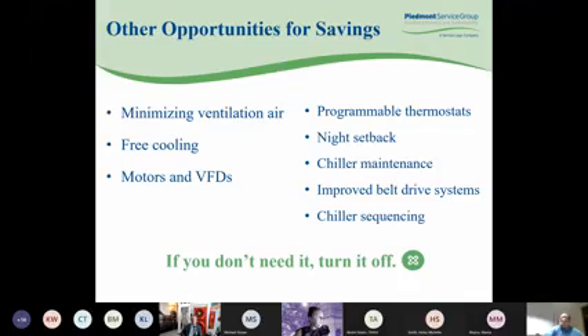Premium efficiency motors is another area. The difference in operating cost between a 92% and a 93% efficient 20 horsepower motor can be between $50 to $120 annually. The variable speed motors is another area that we can look at. Rewinding failed motors is not cost effective in high use applications.